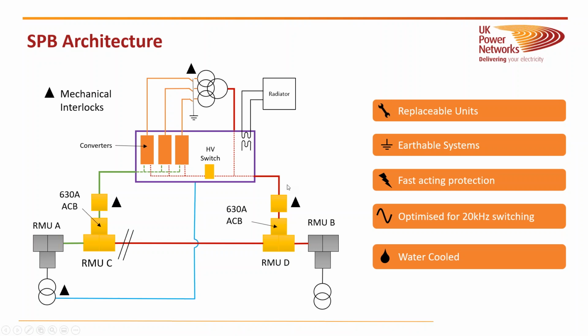So I'm conscious of time, so I'm going to go on to the SPB architecture. I'm not going to have enough time to do this design justice, but I'll give you an idea of what we've got here. The SPB is very different to the SOP. It follows a sort of unified power flow controller architecture. It has 3 voltage source converters, which allow us to transfer up to 5 megavolt amps of power from one feeder to another. But at the same time, you only have to rate the converters for 1 MVA. So these are actually 3 converters all at 350 kVA. And this allows the equipment to be much smaller and therefore hopefully easier to install in more places.